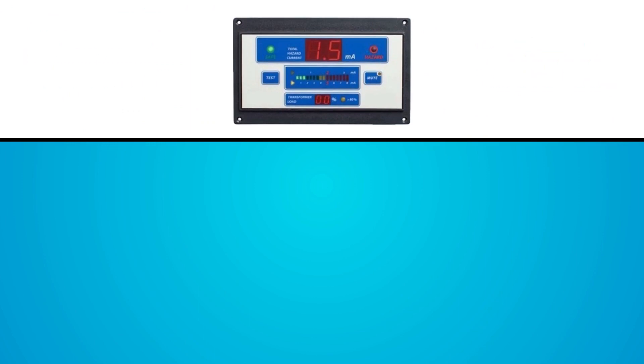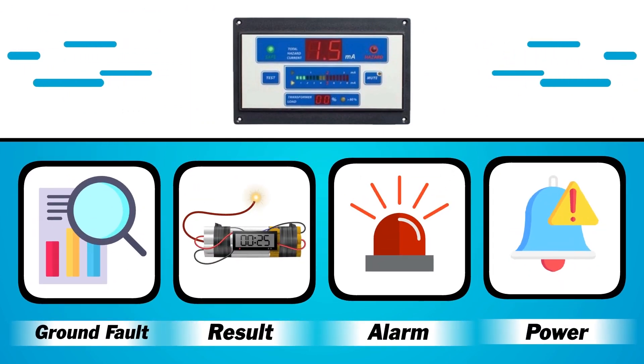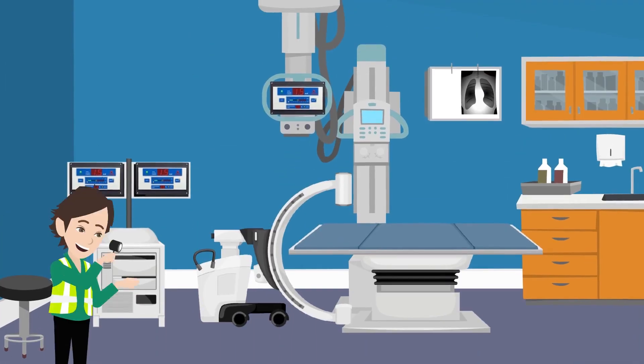In an isolated power circuit, a ground fault would result in an alarm, but power would not be interrupted. According to NFPA 99, hospital isolated power systems must be tested and recertified once per year.